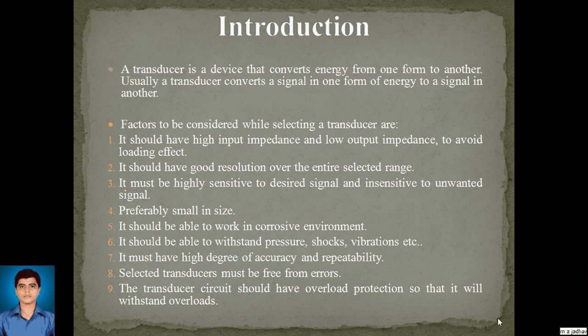Fourth, it should preferably be small in size. Fifth, it should be able to work in a corrosive environment. Sixth, it should be able to withstand pressure, shocks, vibration, etc. Seventh, it must have a high degree of accuracy and repeatability. Eighth, the selected transducer must be free from errors. Ninth, the transducer circuit should have overload protection so that it will withstand overloads.